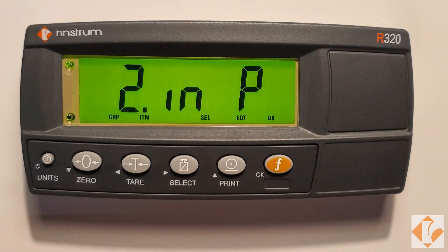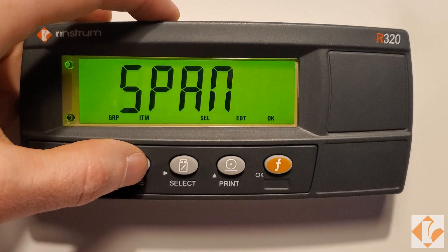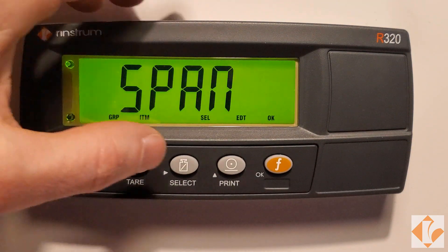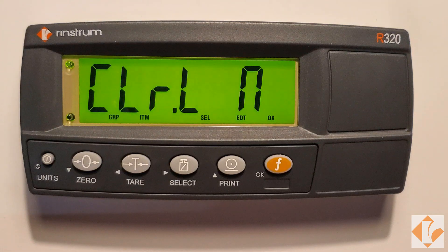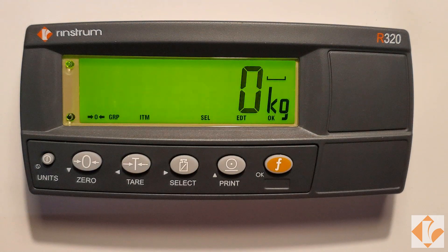Press the F key to capture zero. Press tare two times to get to span calibration. Press select. Clear LIN will be displayed. Press the F key to skip linearity.